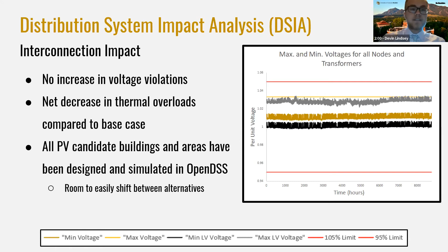On top of proposing the PV transformers, while analyzing thermal overloads, we identified 3 different transformers throughout the UCF grid that routinely experience overloads well above their emergency power ratings. The first 3 rows in this table show each of these units with their existing ratings, as well as the increased ratings of our recommended replacements.